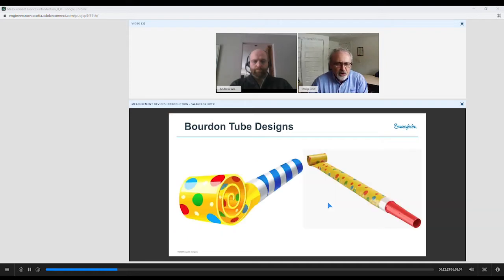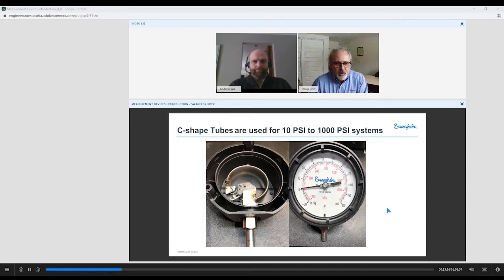Now, how does a Bourdon tube work? If you've ever been to a birthday party, and I'm giving Andrew's daughter a shout out today, it's her birthday, you may have a party horn. We think of this end as the pressure connection going to your system media. As you apply pressure through the socket to the Bourdon tube, it wants to straighten out. And that is then turned into a mechanical motion to give you a readout on the dial or the face of the gauge. Once you've applied pressure, it straightens out. And when you reduce the pressure, it starts to come back. So that's how the Bourdon tube actually works inside the pressure gauge.